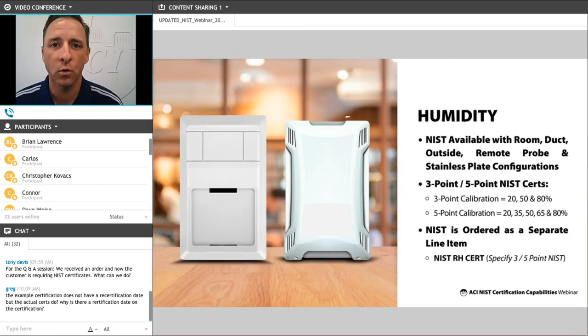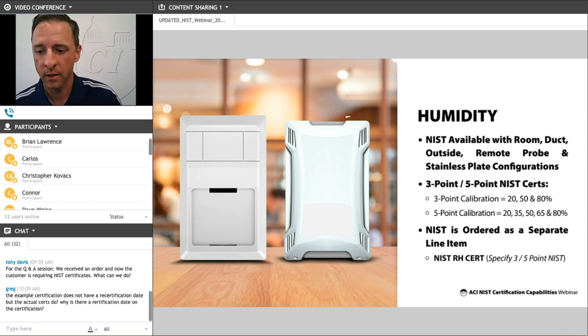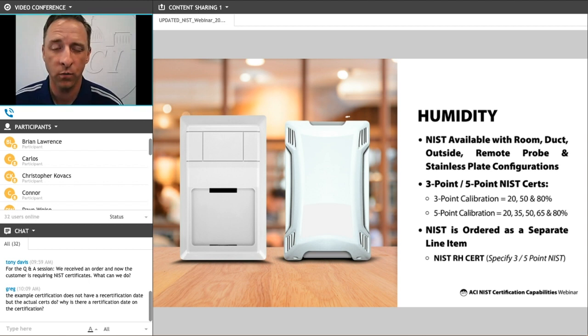Our humidity sensors are also available with NIST certs in 3 and 5 points. Most applications are available, including room, duct, outside, remote probes, and stainless plates. To get a cert for humidity sensors, you add a separate line item to your order. For example, if you need a 2% accuracy duct humidity sensor, you specify the part number A/RH2-D, and then add a second line item for NIST RH CERT — either 3 or 5 points. By default, if the number of test points aren't specified, we default to a 3-point cert for our humidity sensors.